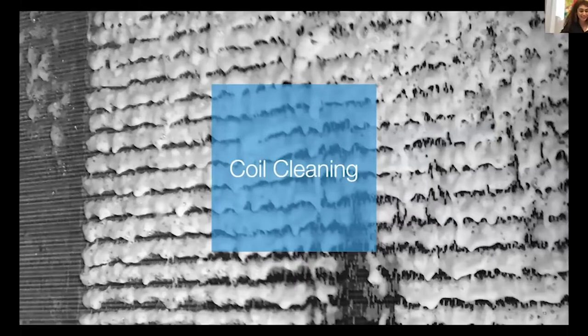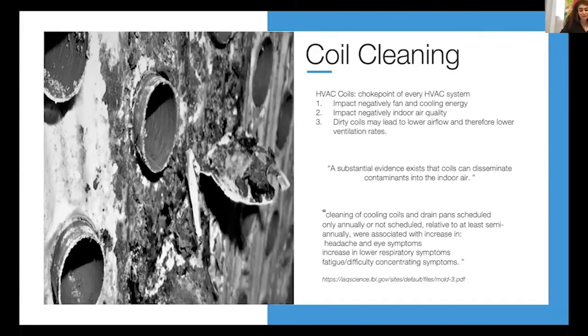My next topic is coil cleaning. Similar to filter bypass, I don't think we talk enough about coil cleaning, but it is important. It's important because all the air in our buildings goes through coils, heat exchanger coils, which can be heating coils, and in our case, it's more about cooling coils. Coils can impact your energy, can impact your indoor air quality, and can also disseminate pollutants back into the airstream. And I put here a study from the largest indoor air quality database ever done in the United States. They basically say that if you clean your coils twice per year versus one time per year, you will actually have a decrease in respiratory symptoms and also in productivity loss. So it's important to take care of your coils.